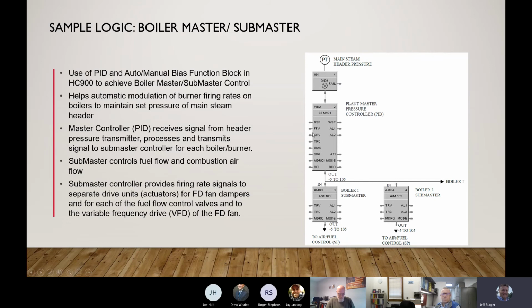Also in these blocks, you have several pins, inputs and output pins. These do not need to be all connected within the configuration. These are just functions that you can use to hook up. Maybe I want to hook up a digital output to an alarm. Maybe I want to retransmit a working set point. There's a lot of different pins here that give you functionality to either retransmit or feed a signal into this function block from somewhere else in the program.